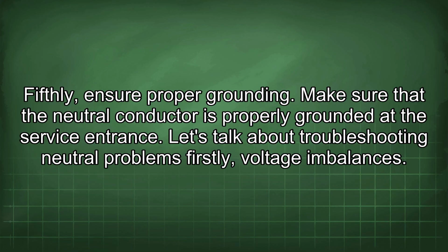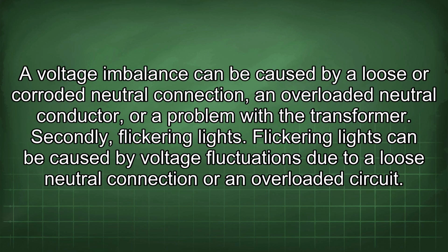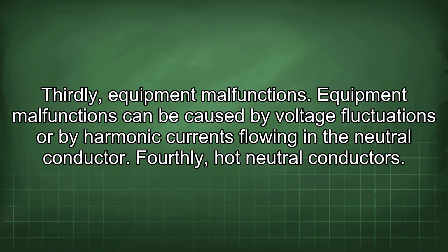Let's talk about troubleshooting neutral problems. Firstly, voltage imbalances. A voltage imbalance can be caused by a loose or corroded neutral connection, an overloaded neutral conductor, or a problem with the transformer. Secondly, flickering lights. Flickering lights can be caused by voltage fluctuations due to a loose neutral connection or an overloaded circuit. Thirdly, equipment malfunctions. Equipment malfunctions can be caused by voltage fluctuations or by harmonic currents flowing in the neutral conductor. Fourthly, hot neutral conductors.